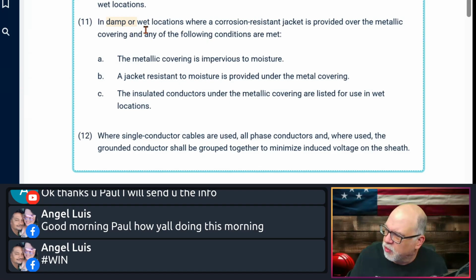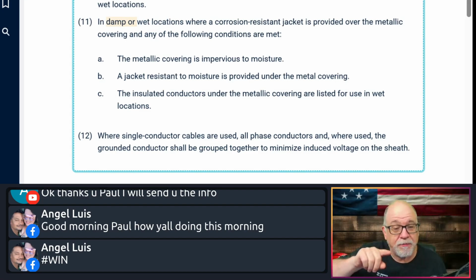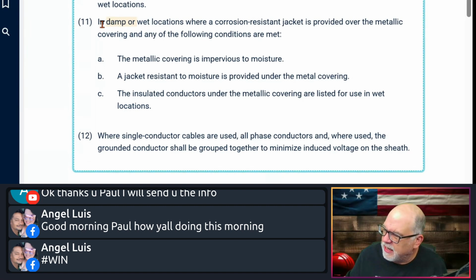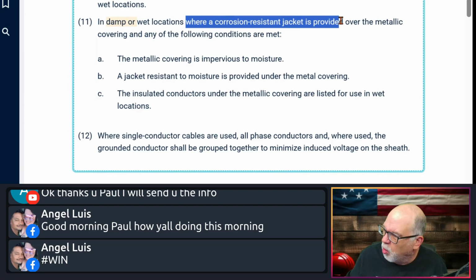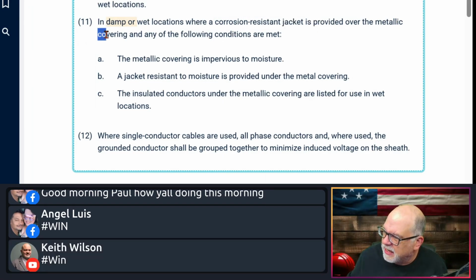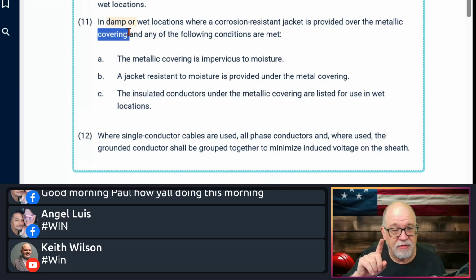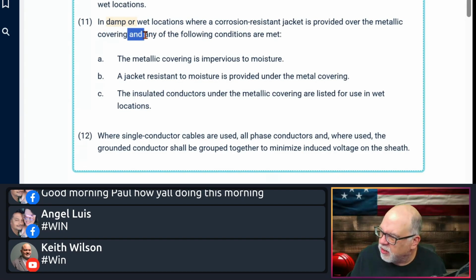So let's look at it. The first one, and this is going to show you the difference in the different types of MC. It says, in a damp or wet location where the corrosion resistant jacket is provided over the metallic covering. So when it comes to these products, it's saying, okay, if it's a damp or wet location and you have a corrosion resistant jacket provided over the metallic covering, so it has to have a corrosion resistant covering, which, by the way, PVC material is.